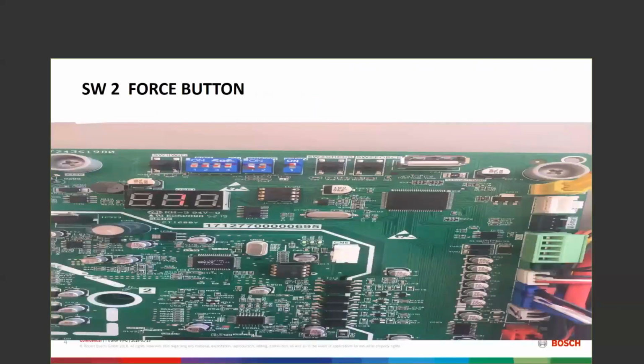The SW2 button is nothing more than the force button. The force button allows us to do something to this machine upon our demand. I can allow the unit to run in the air conditioning mode, push the force button, and the machine sees what I've done, and it will ramp itself up or down toward that 100%. So when we say this is a 20.5 SEER rated unit, it was at 100% capacity when it achieved that number. Anytime I am at less than 100% capacity, I'm at a greater SEER rating, a greater EER rating, and I'm using fewer watts than at the 100% level.